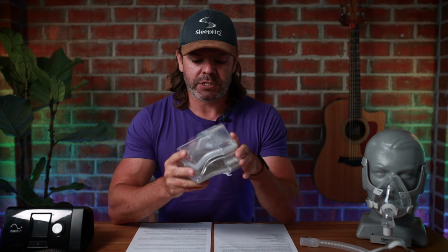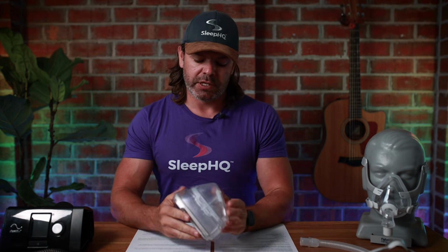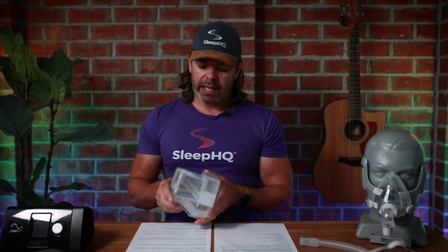Humidifier chambers, the water tubs, they should last 12 months if you're looking after them, using distilled water or cleaning them out on a regular basis. There's no reason why they shouldn't last 12 months. That being said, it's a little bit of a common flaw with these ResMed tubs that they sometimes start to leak out the seal at the bottom between the metal plate and the plastic. So if that happens, I would recommend you hit up ResMed for a warranty replacement, because it is a known flaw. Otherwise, if you can't be bothered with that, just go and grab a new one. They're not that expensive. All right, but 12 months at least for the water tubs.